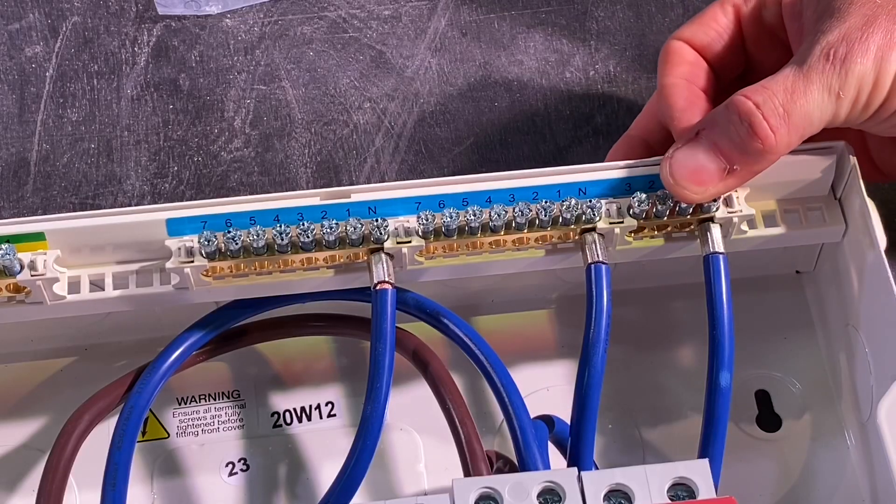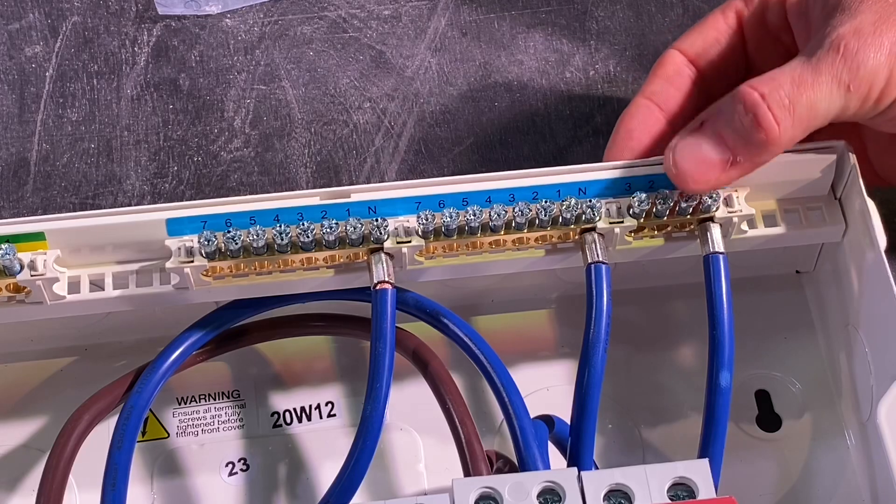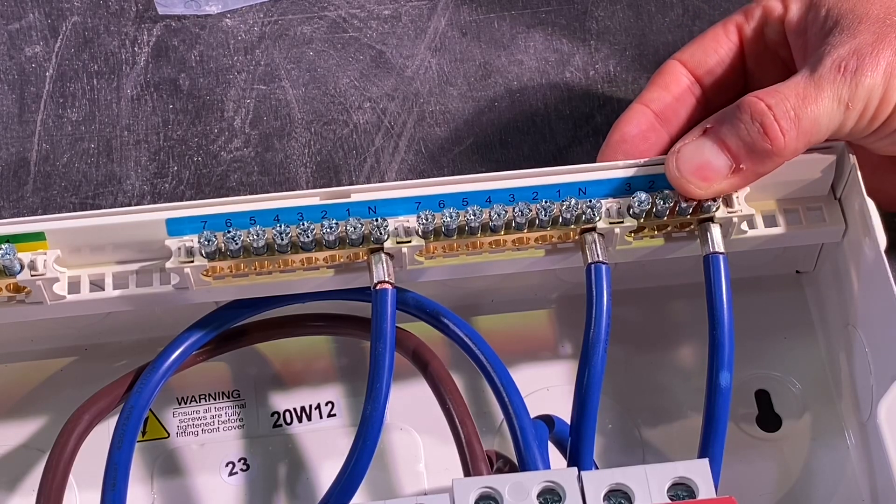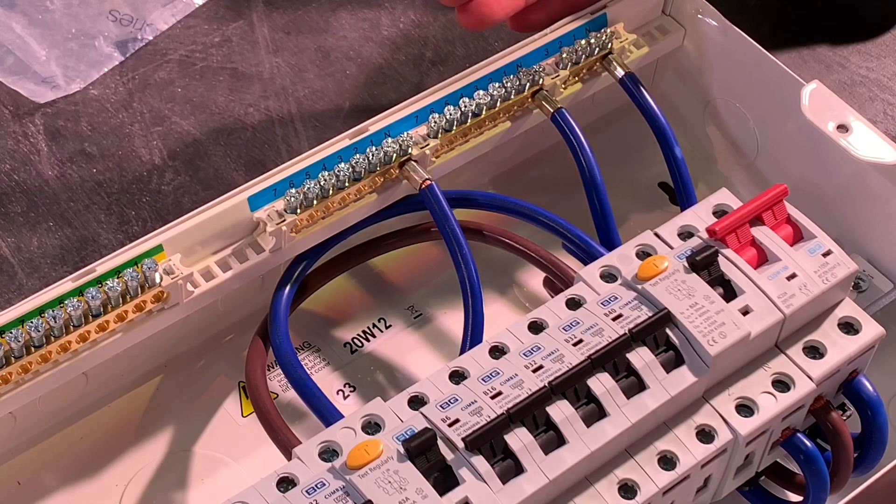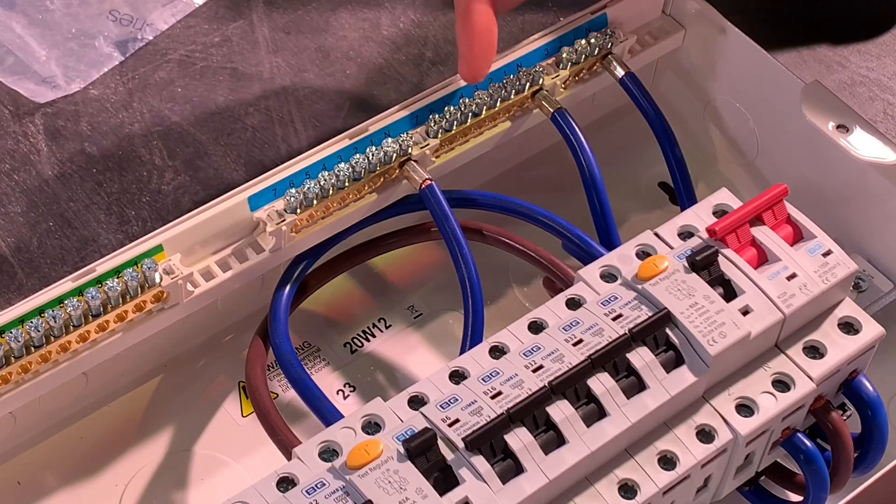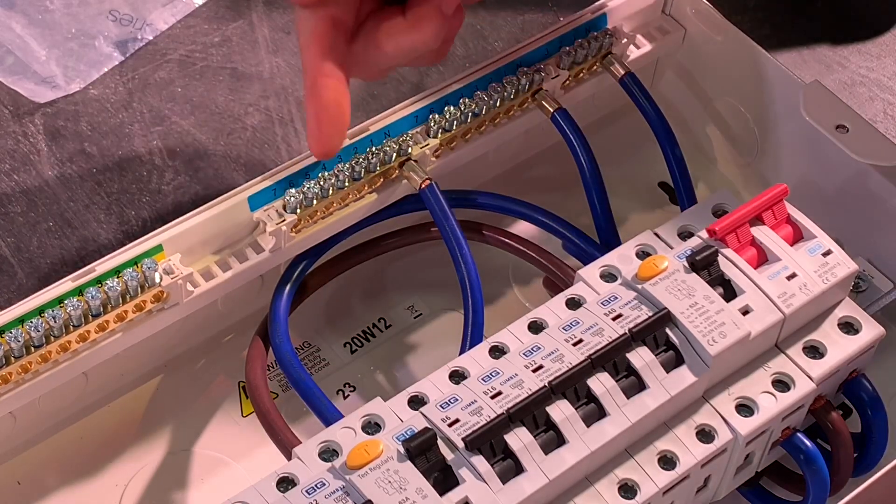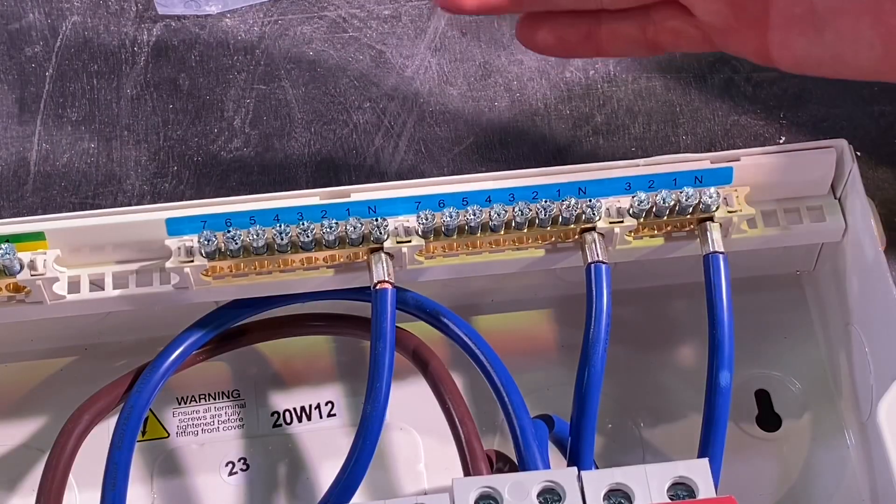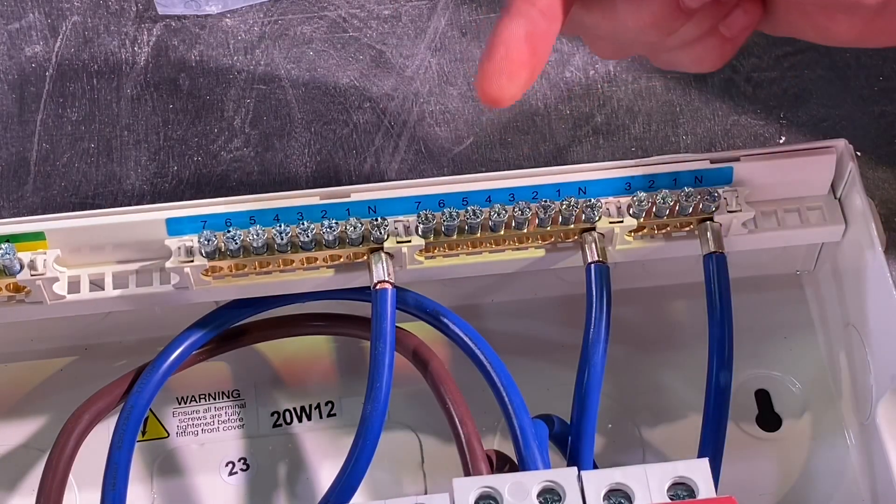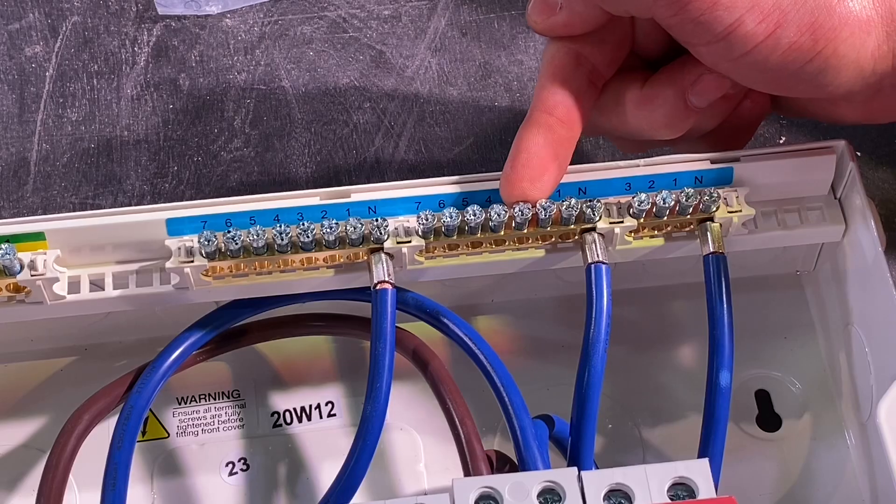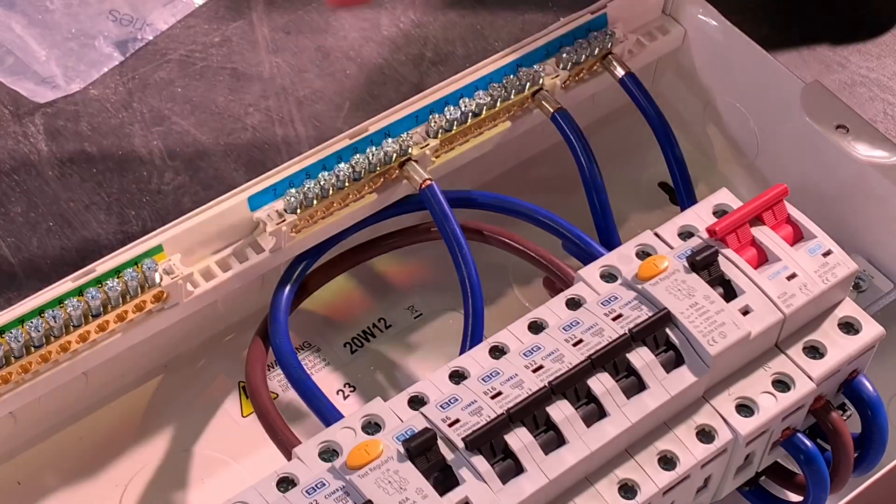We've got a three terminal neutral bar here in case you wanted to rearrange the board to have a high integrity circuit, maybe a steel or armoured feed in another consumer unit. You've got seven neutral connections here and seven here, even though it's a 5-5 split, meaning you could potentially have seven circuits on one of your RCDs and three on the other or mix and match to suit.